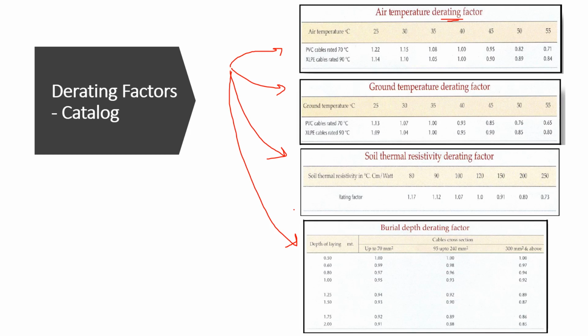Let's say, for example, our cable is installed in a cable duct or in air. Since it is installed in air, we need only the first one, the air temperature derating factor. So this cable is installed in air or in a duct. Now, what is the type of cable? Is it a PVC cable or a cross-linked polyethylene cable? For example, I am choosing a PVC cable.